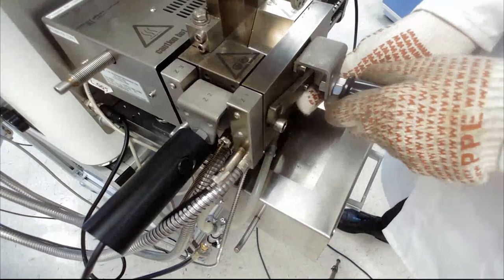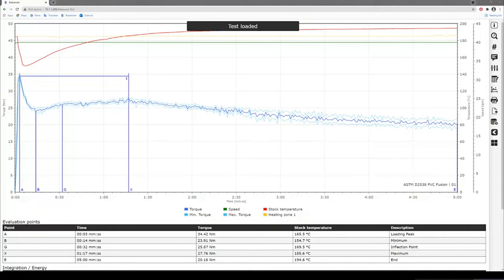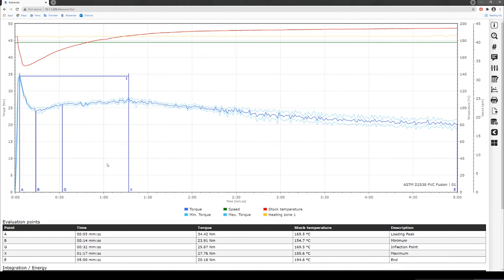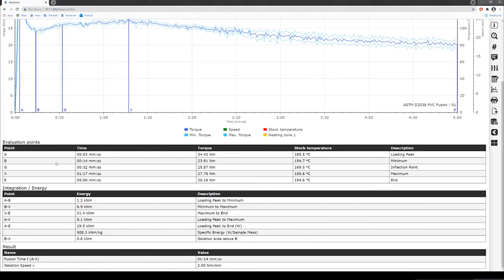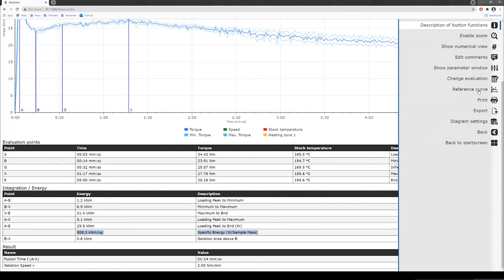At the software you can see what the test data did. We see our fusion evaluation according to ASTM D2538. We have our loading peak, our minimum, our gelation point where there's the maximum speed of the fusion, and the highest point afterwards which is point X. This is then considered the fusion time and our end point. If you go and scroll down you will see all those points and also then the energy put into the system. I can just create a reference curve out of that, and for the next test I would be able to compare against that, or you take multiple versions and create an average curve out of that.